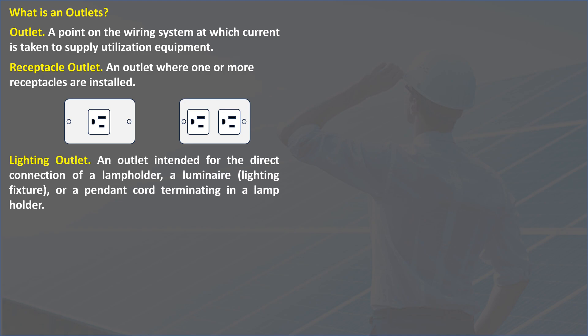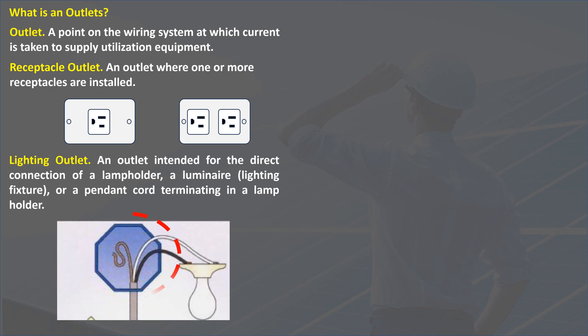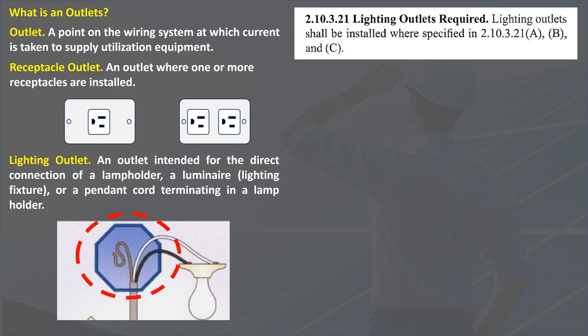There is also a lighting outlet. By code definition, a lighting outlet is an outlet intended for the direct connection of a lamp holder, a luminaire, a lighting fixture, or a pendant cord terminating in a lamp holder. The code rules for lighting outlets are covered in Section 2.10.3.21.